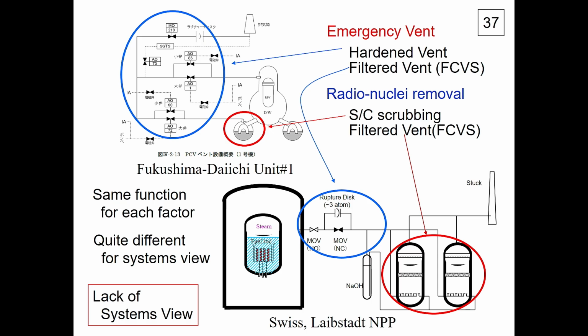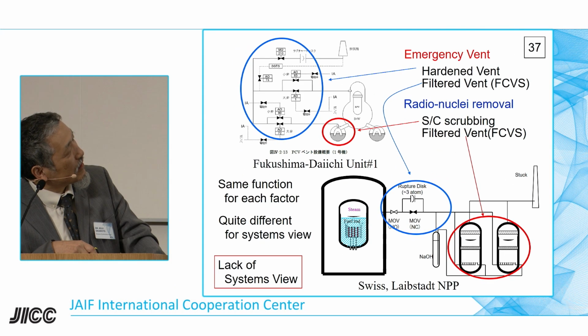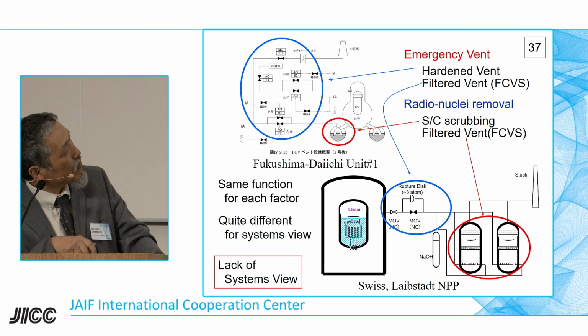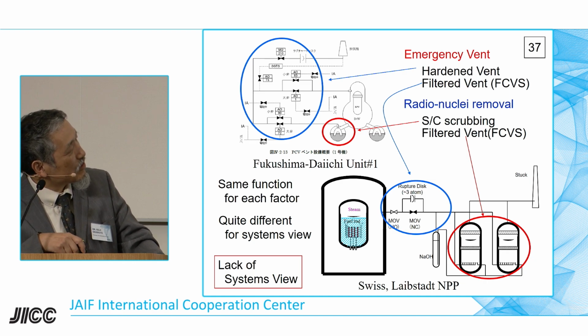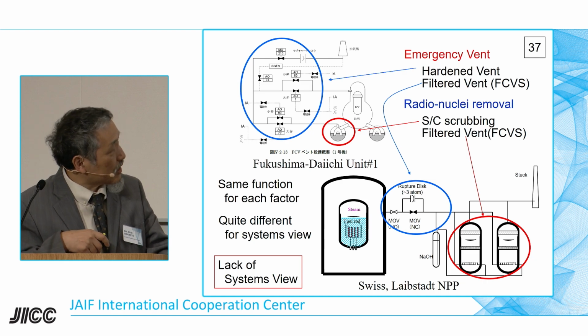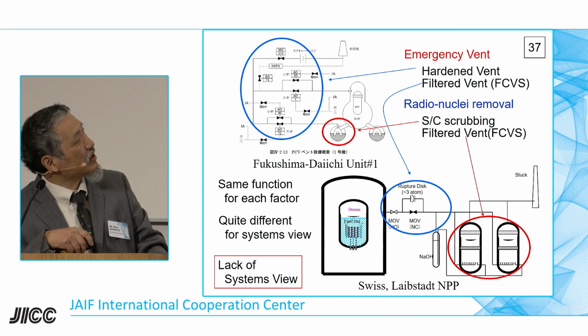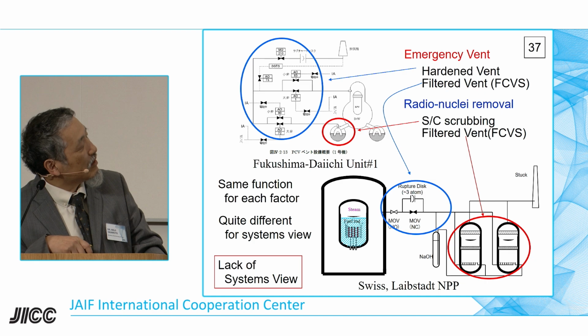Comparing with the Swiss system, there, if pressure increases, it automatically opens, and the filtered venting system is separately installed. So both systems have the same function, but the viewpoint of the system design is different. This means for station blackout or other accident considerations, they are very different systems.